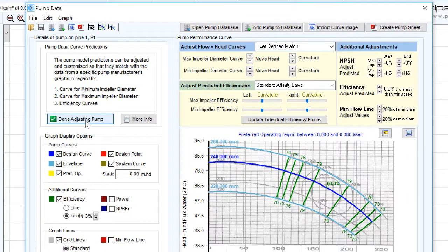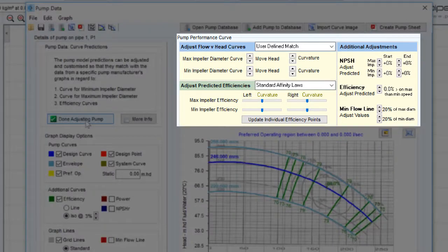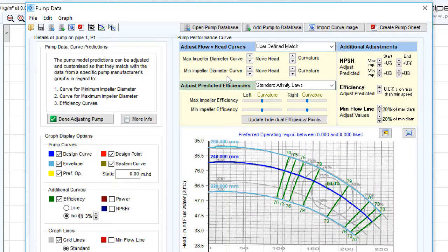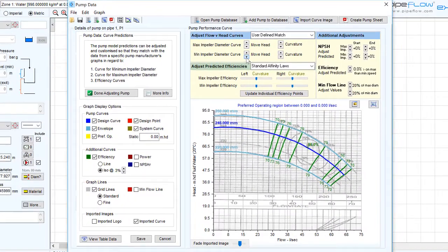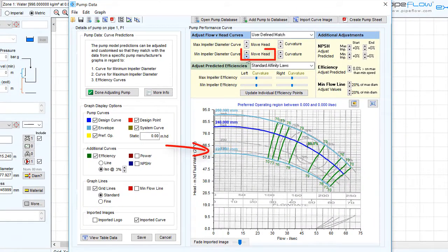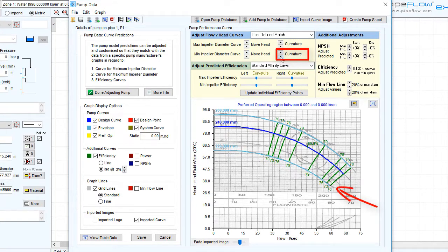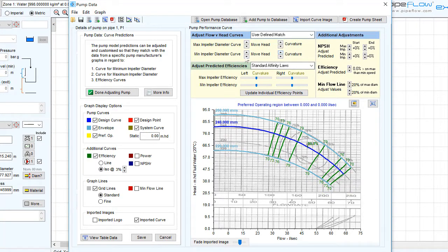However, in this case, for more accurate modeling of pump performance, we will use the Adjust Pump Model tools to adjust the curvature and efficiency points for the predicted curves at the maximum and minimum impeller diameters. The Adjust Flow vs Head options, as seen in the previous video, can be used to adjust the shutoff head and the rate of curvature for the minimum and maximum impeller diameter curves.